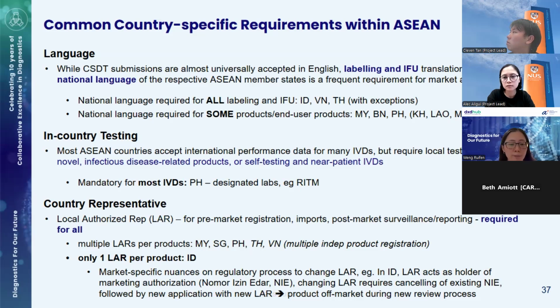And second of all, I think while most ASEAN countries accept international performance data for many IVDs, local performance data is sometimes required. I think especially so for products that are considered high risk, novel, or intended for infectious disease management, or intended for self-testing or near-patient testing. I think the major exception is the Philippines, which actually requires in-country testing data by its designated labs for most IVD products.